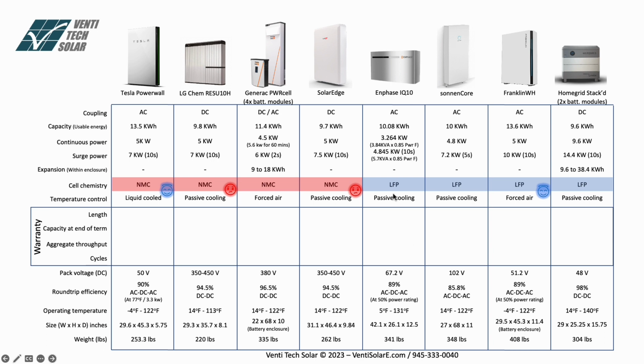On the LFP, temperature range is not too much of a concern, so they can push the limit to 131 degrees Fahrenheit. Again, this is passive cooling. They have to raise the low end. The LFP batteries cannot be charged at freezing temperatures, so I'm expecting that this technology will disconnect the battery when it needs to be charged below freezing. So the 5 degrees Fahrenheit could be a discharging temperature, not charging necessarily. So this is still pushing the envelope, but acceptable. The SonnenCore is more conservative because it has passive cooling, so 14 degrees to 122 degrees. That's probably what I would like to see on LFPs.